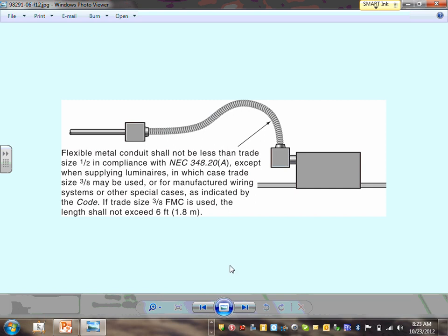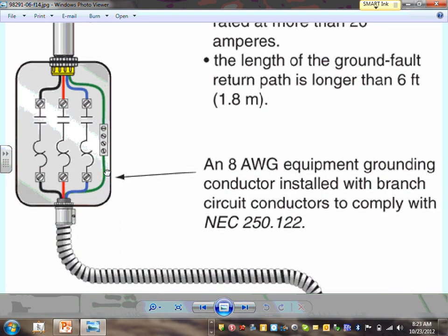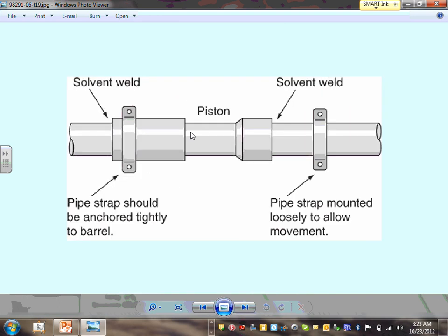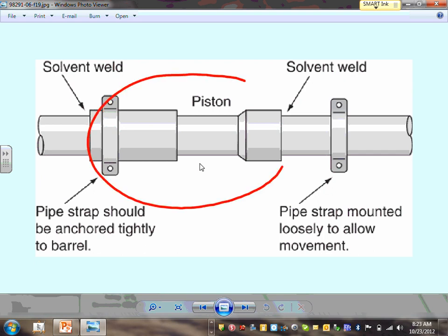Here's what tying to equipment looks like. I can't emphasize enough: look at the green conductor that you have to pull inside the flexible metallic conduit. Always pull that equipment ground conductor, because the flexible metallic conduit itself is not qualified as an equipment ground conductor. Exceptions apply for six feet or less at 20A for fixtures, but for mechanical equipment, always pull an equipment ground conductor. For PVC conduits outdoors, you need expansion fittings because non-metallic conduit expands and contracts significantly with temperature changes - from 100 degrees Fahrenheit down to 25 below in Minnesota.